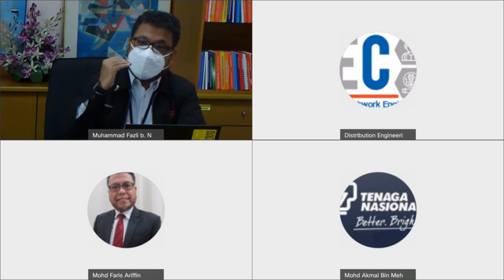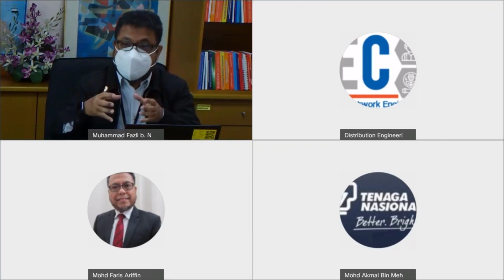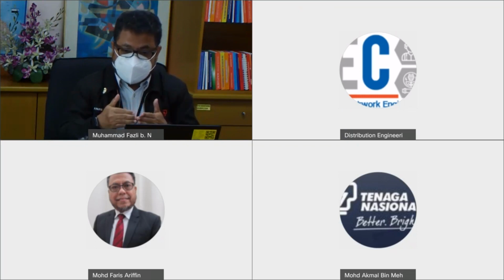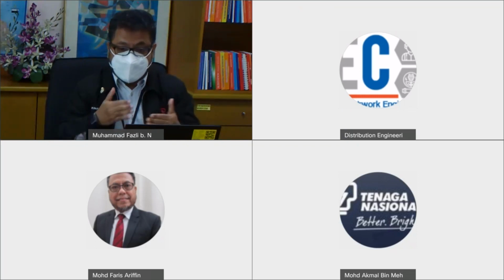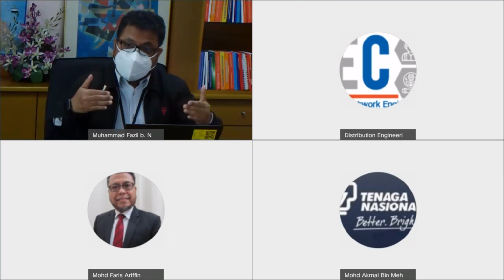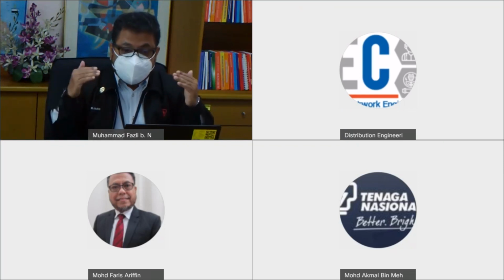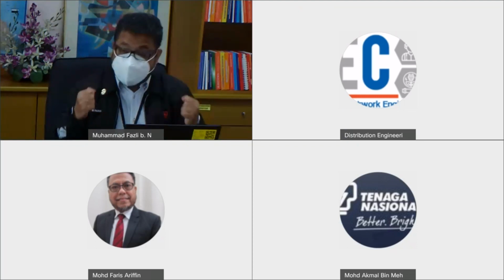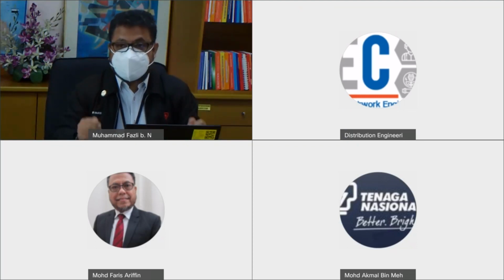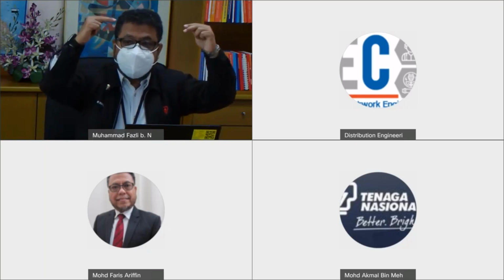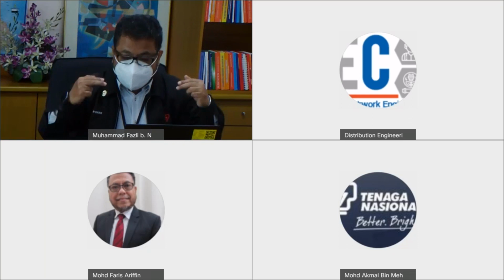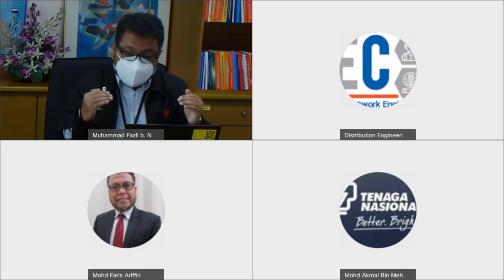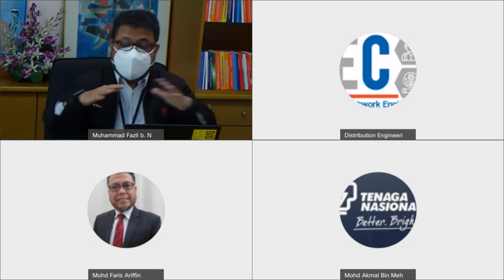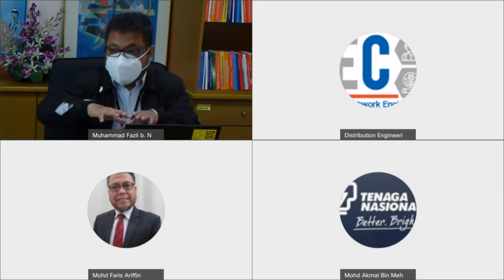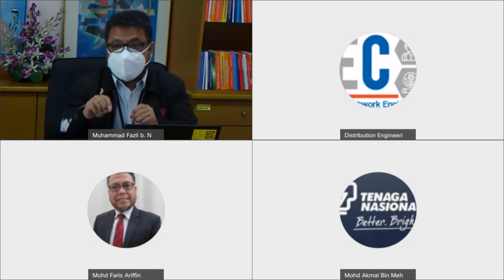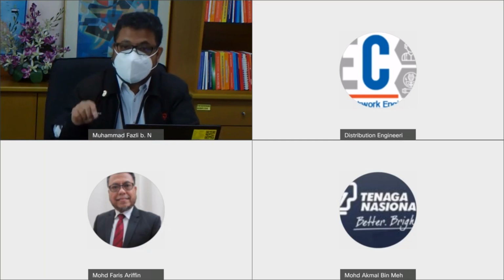It's very, very high at that point of time. So instead of using mesh, we use the counterpoise tape with the X formation, so that at the four corners, it can dissipate the lightning current to ground as soon as possible, because the ground potential rise is very high. So it needs to be discharged very, very fast to the ground. Unlike using the mesh, even if you have the mesh also, it will not go throughout the mesh. It will only concentrate on where the lightning current is being injected to the ground.